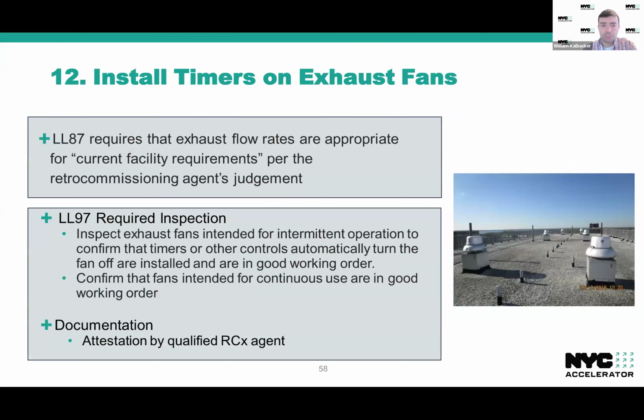87 is a little bit different in its requirements for exhaust. It's basically saying that 87 wants you to ensure that exhaust flow rates are appropriate for facility requirements. The 97 requirement here is that exhaust fans be inspected. If they're supposed to be operating intermittently, then you want to make sure that their timers and controls are turned on automatic and that they are sequencing as they should. For fans that are intended to work continuously, you just want to make sure that they are in good operating condition. The documentation requirement here is that an attestation is filed by the RCX agent.